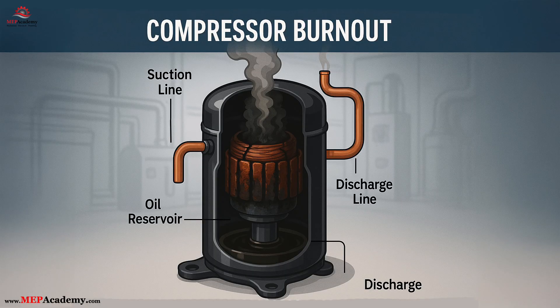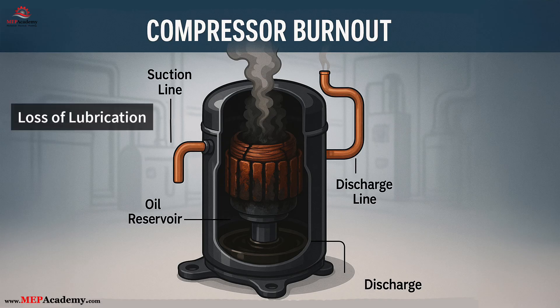Common causes: loss of lubrication. Lubrication is often lost due to refrigerant leaks or flooding that washes oil out of the compressor, leading to metal-on-metal contact and eventual burnout.